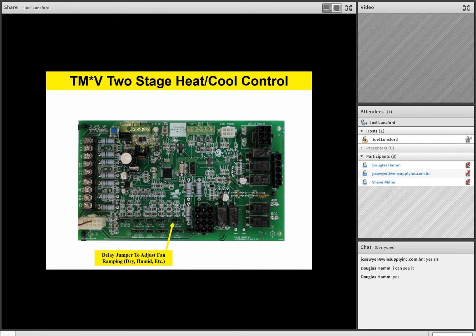You get the idea. So these different airflow profiles, these delay profiles, what it does is it ramps the fan in the cooling mode of operation to pull out extra moisture if you have it on the humid profile. To give an example, if you have it on the B humid profile, I just happen to remember this one because I live in Mobile, Alabama, where it's so humid all the time in the summertime. On the humid profile, on a cooling call, the fan starts out at 50% airflow for 1.5 minutes, and it ramps up to 85% airflow for another 6 minutes, and then it'll finally ramp on up to 100% airflow if the call for cooling is still there.